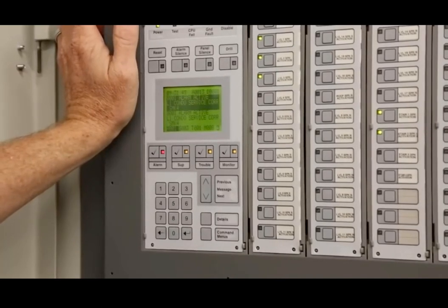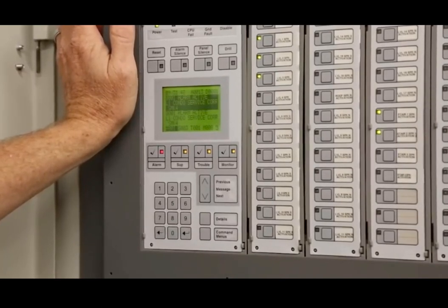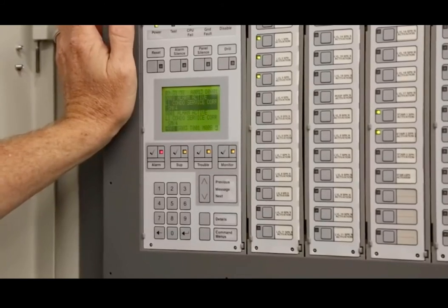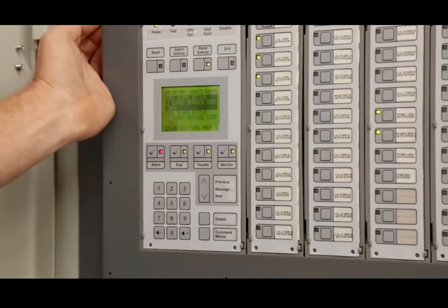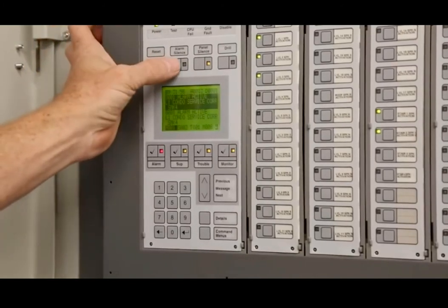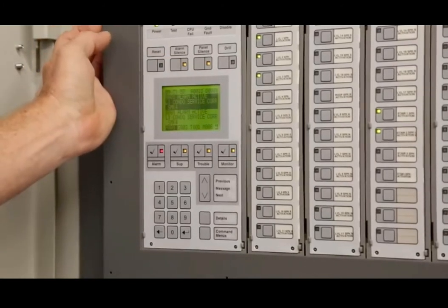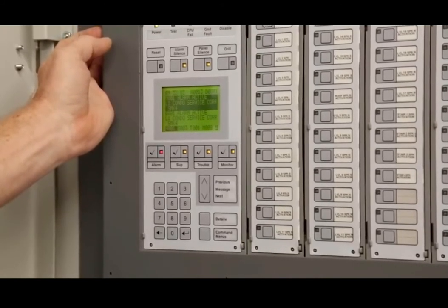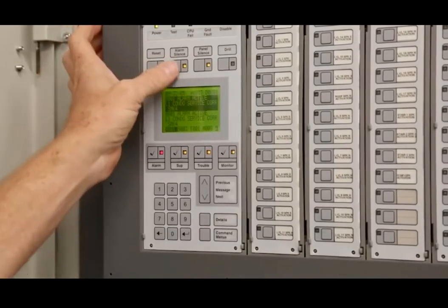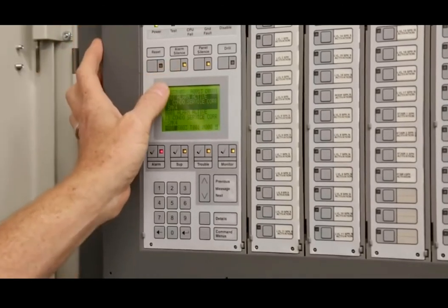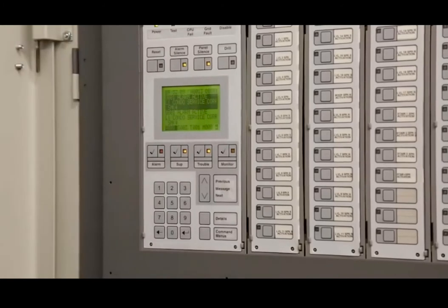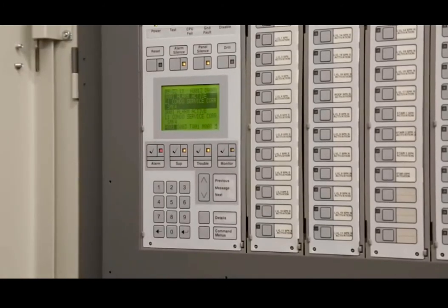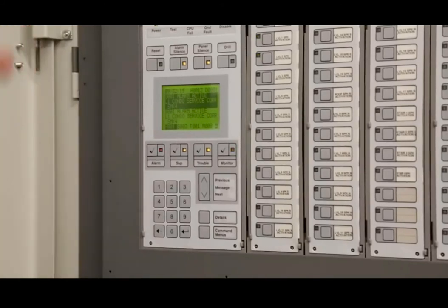So that's another subject. But let's just say you already investigated, everything's good, you know it's a false alarm. We can hit panel silence, that only shuts up the panel. Alarm silence will basically shut the strobes and speakers off, okay? Now, that's a toggle feature, okay? So if you come in here in a panic, hit this thing twice, what did you just do? You turn it off and turn it right back on again. It's a toggle. Every time you hit it, it toggles back and forth.